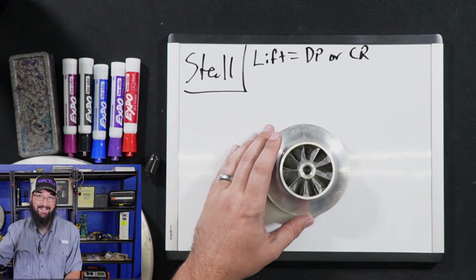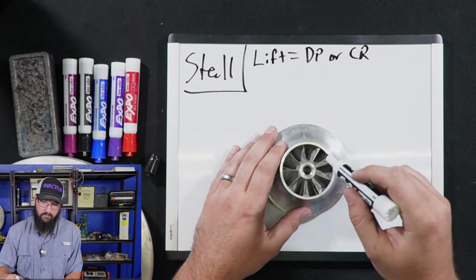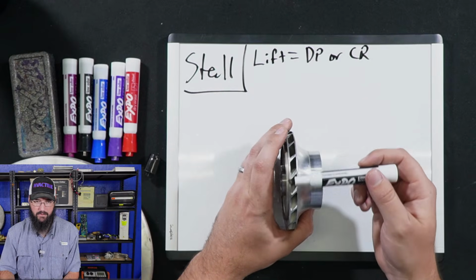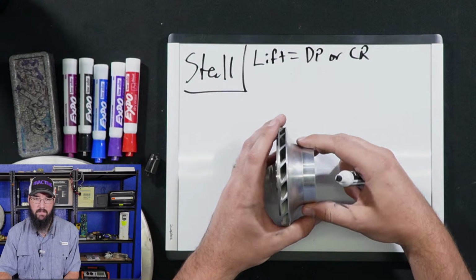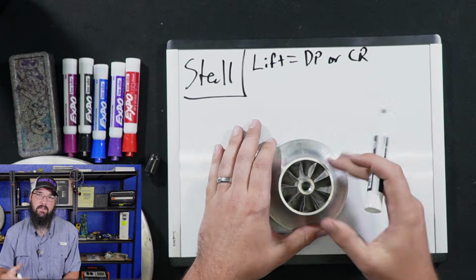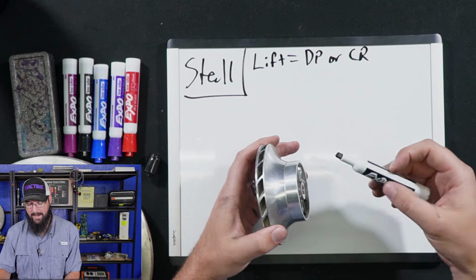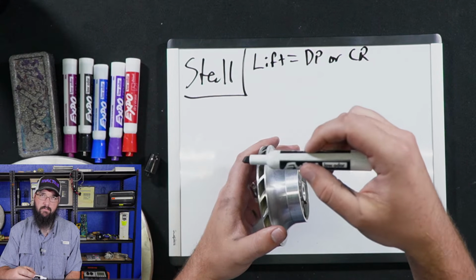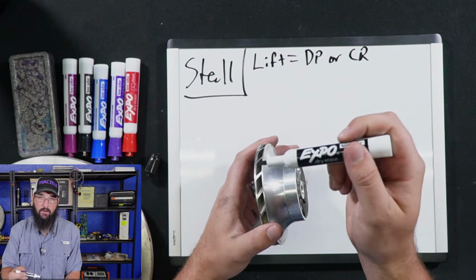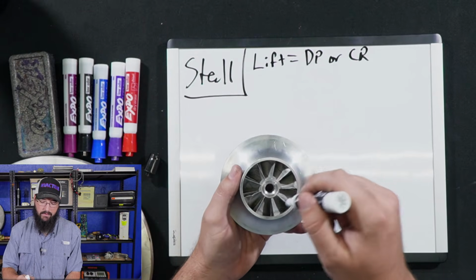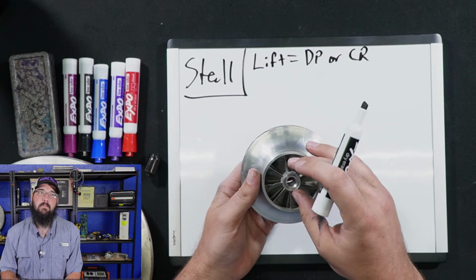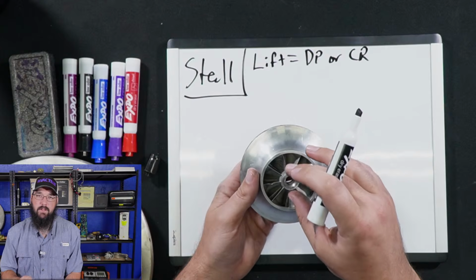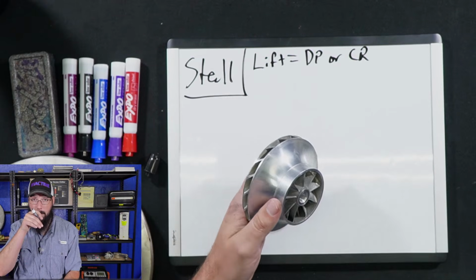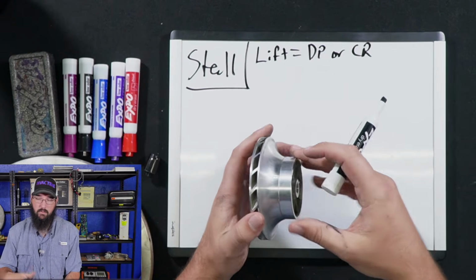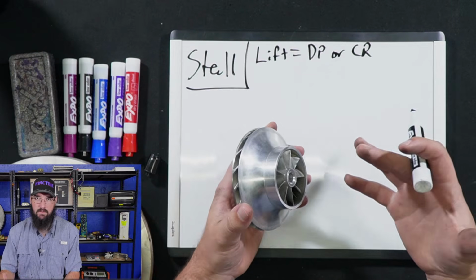So when we get a high lift, we get to a point where our ability, so we have the suction side of our impeller here, we have our discharge side here. Our ability to then have that refrigerant come in and sling out of the impeller gets limited because we can't add enough energy to overcome how much difference we have between the outlet and inlet side of the impeller. Because keep in mind, this is not a positive displacement compressor. This is aerodynamic, so all this is just open space in between here with some vanes. Just like a blower motor, it's the exact same thing, just moving air instead of refrigerant. Same exact concepts though.